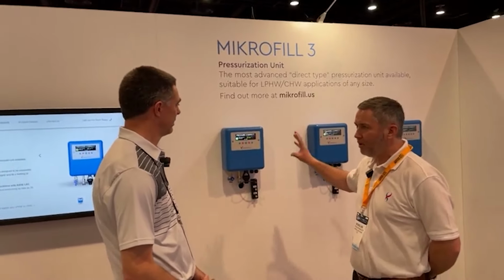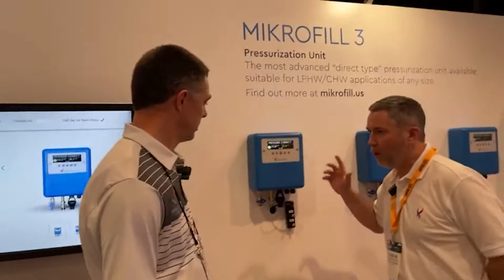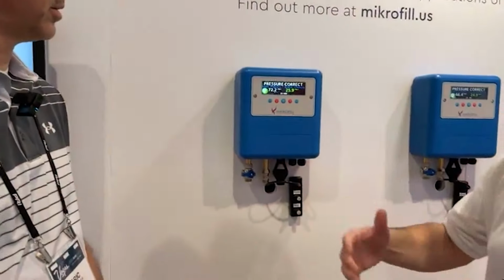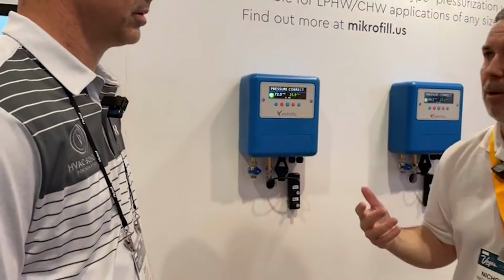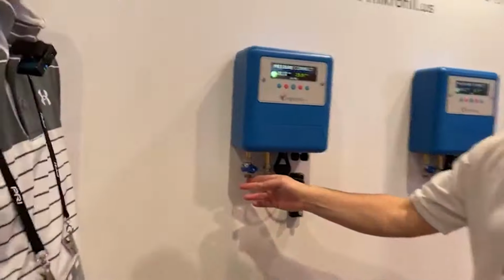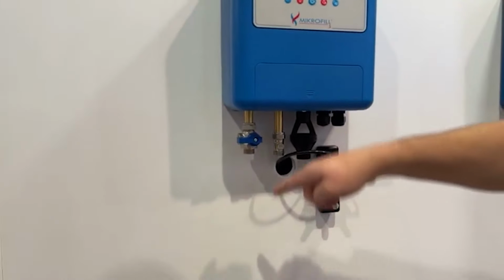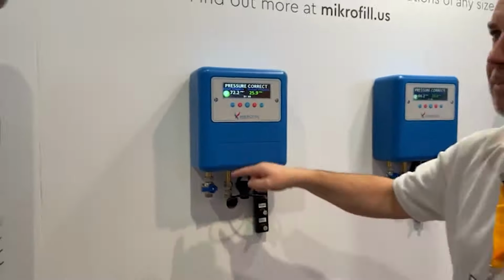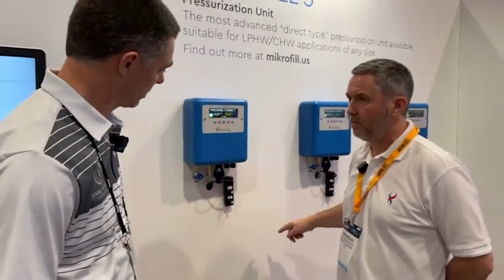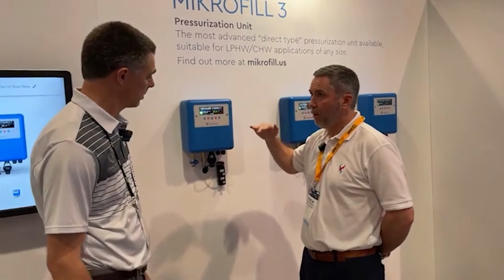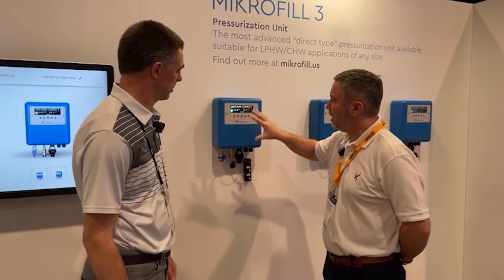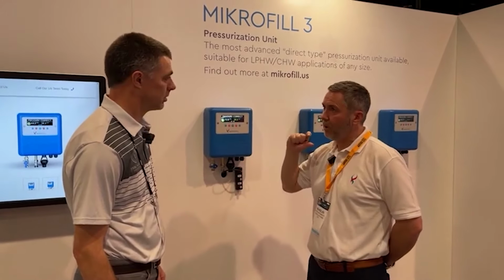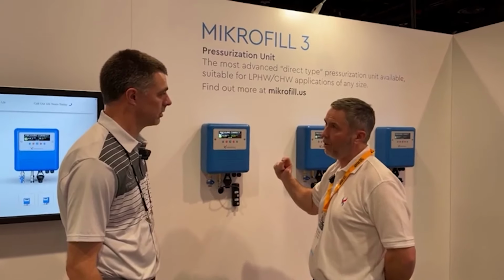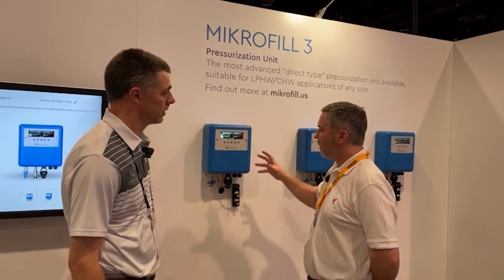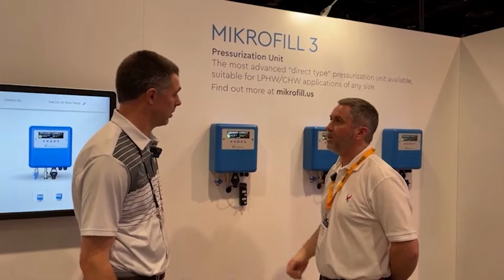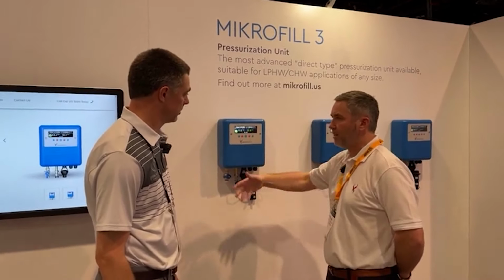But as you can see, it's a wall-mounted unit. Unlike conventional units that use pumps and tanks to fill and subsequently top up systems, it utilises mains or boosted mains water through a series of solenoid and check valves to administer water to a commercial system. Once you hit a target pressure for that relative system, it stops, closes valves and opens a drain valve that exhausts a small amount of water that would fill an egg cup. It creates the relative backflow protection required for the US, so that prevents any inhibited water getting back to the mains.